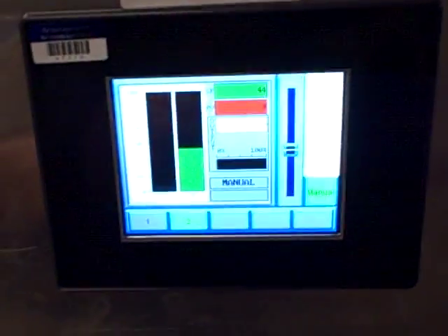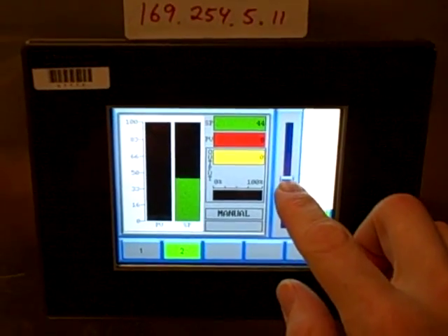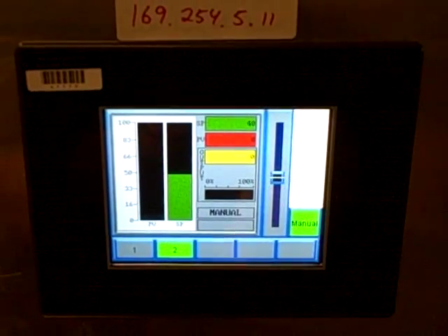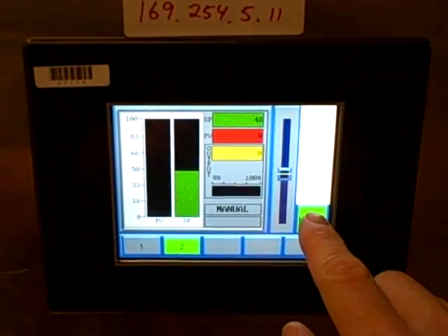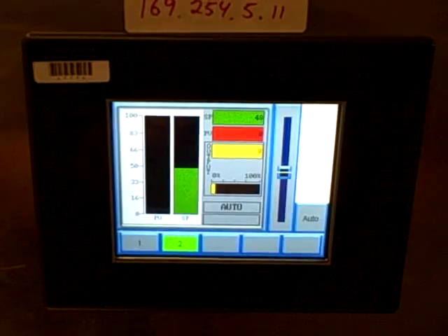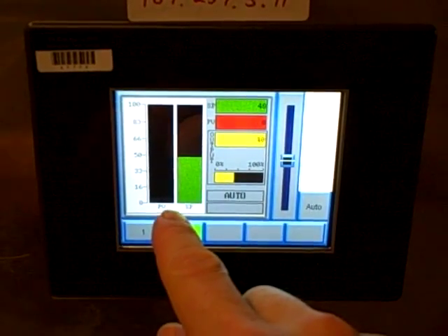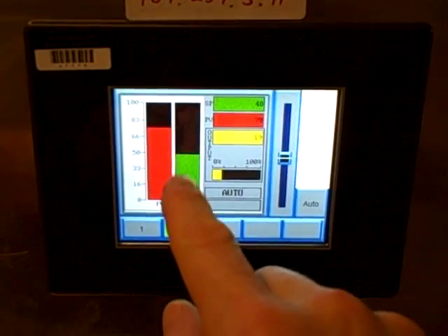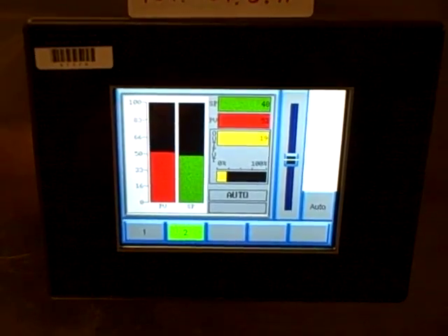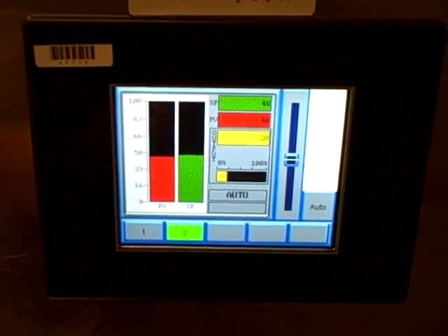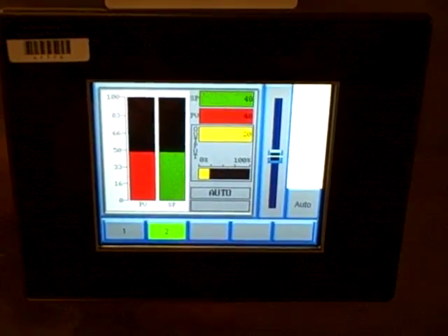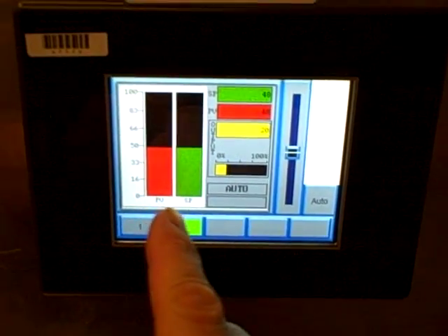So from here, I can take control over that PID instruction in the MicroLogix 1100. In this case, I can adjust my set point where I want it to be, and then I can switch from manual mode into auto mode. And when I do that, it begins ramping up the output, the turbine comes up to speed, you'll see a red bar here, overshoots a little bit, and then corrects back to set point.